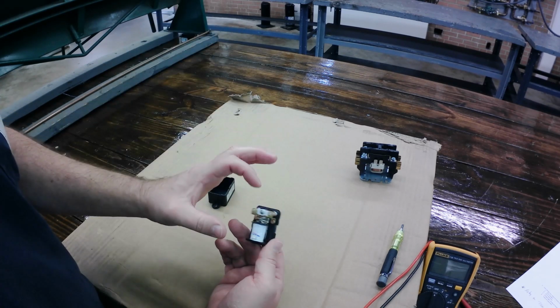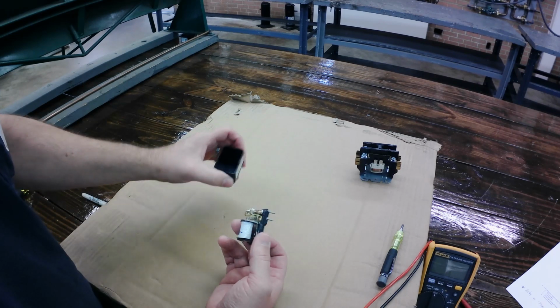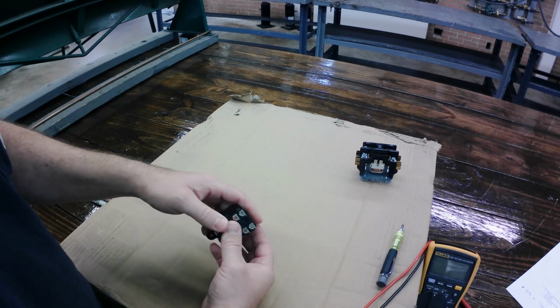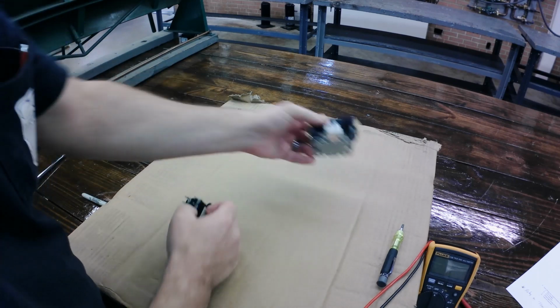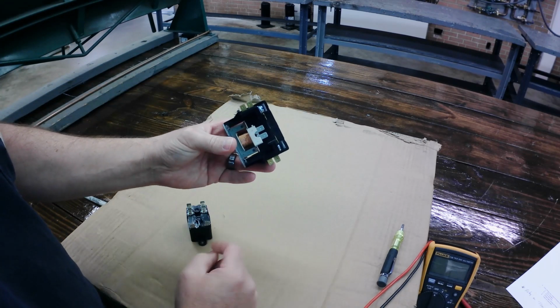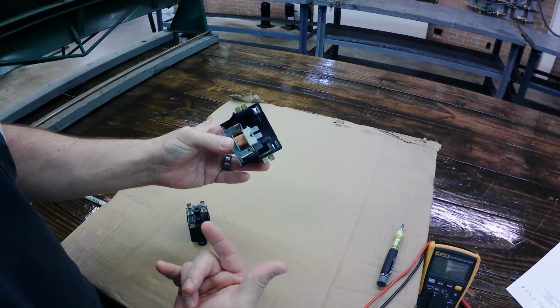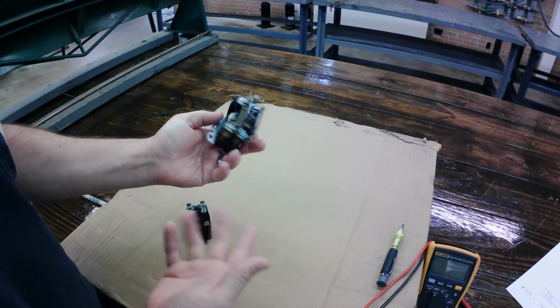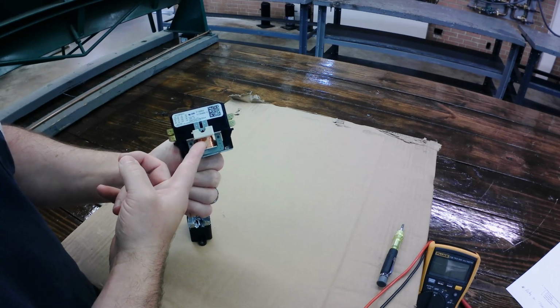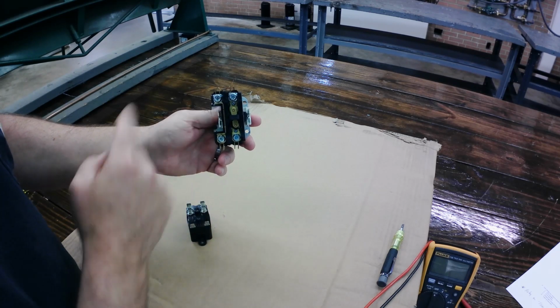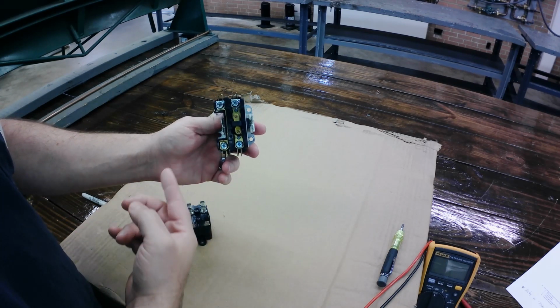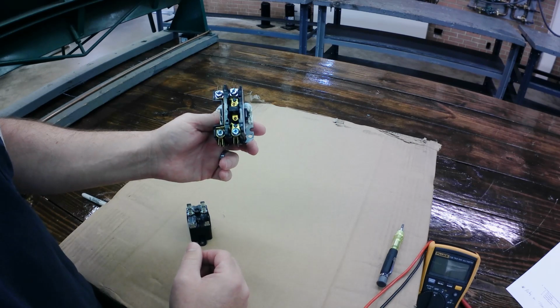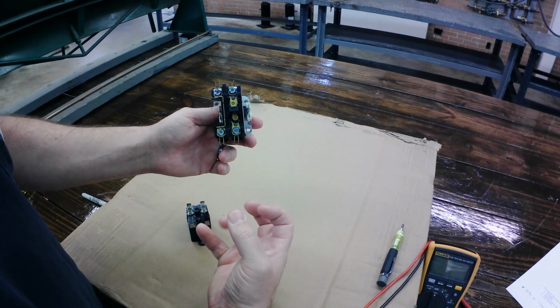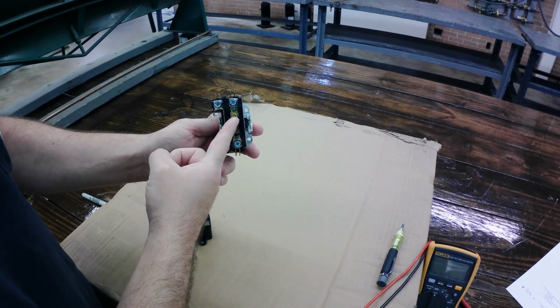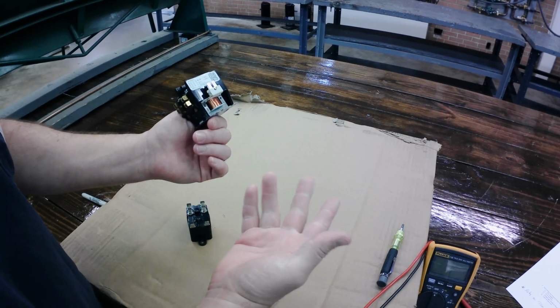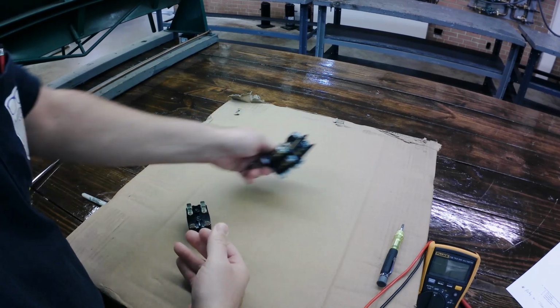Now, if either part is bad, then you get a whole new relay. So if you go to a contactor and you say, oh, the coil is shorted, we don't replace just the coil anymore. It's not made that way. So you'll just get a whole new contactor. Or in the case of the contactor, if the switches burn up, maybe you had some arcing or pitted contacts on it. If the switch is messed up and the coil is fine, either way, you still replace the whole contactor.